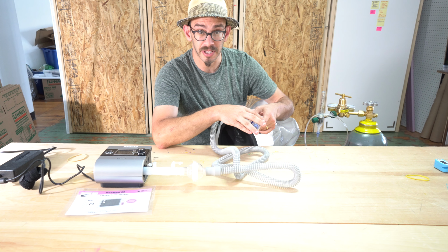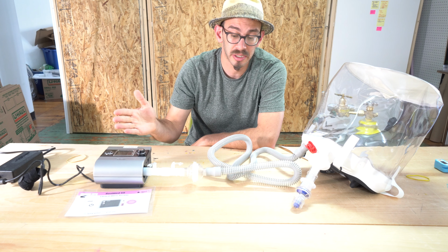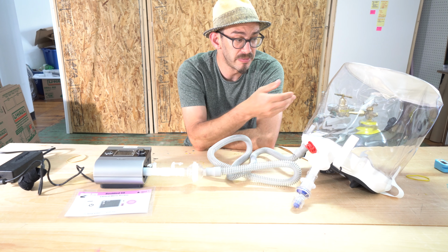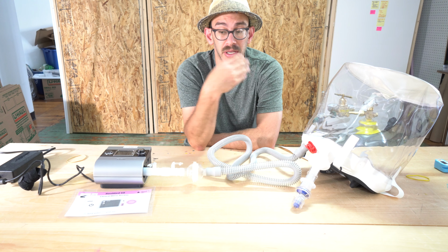The reason for that is we're using this as a commonly available flow reducer. The flow reducer lets us build up PEEP within the hood, but you also want as little flow reduction as possible, because you want sufficient flow to go through that it can continually flush out carbon dioxide and ensure that your patient is not rebreathing old air.